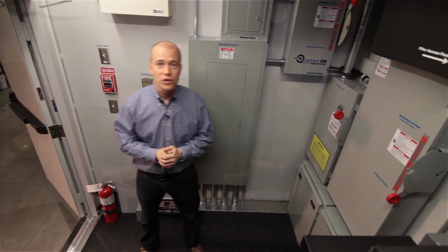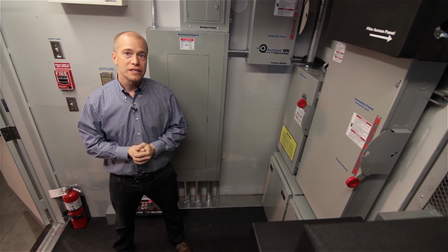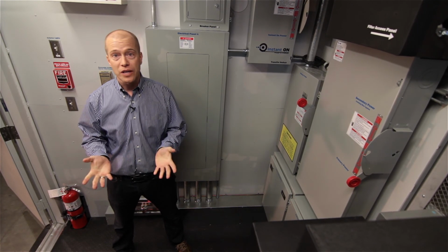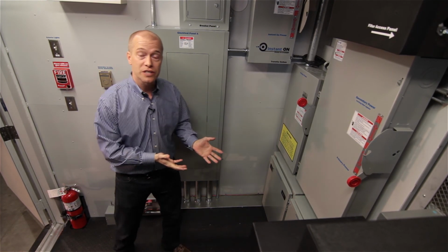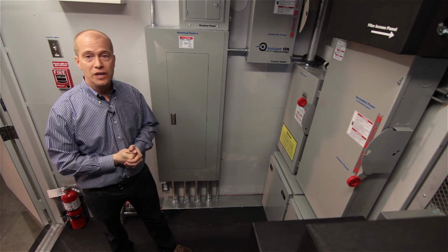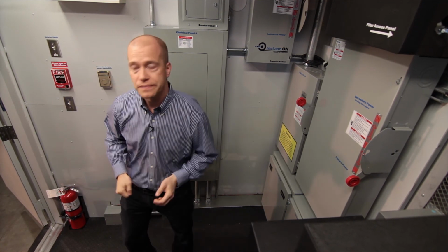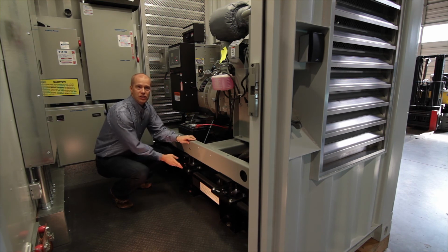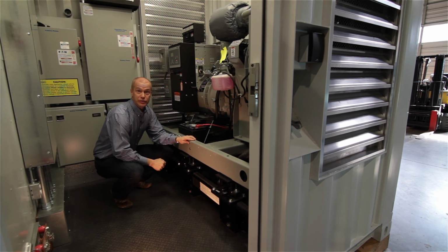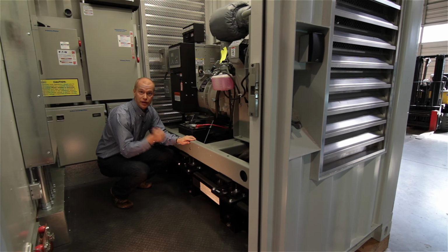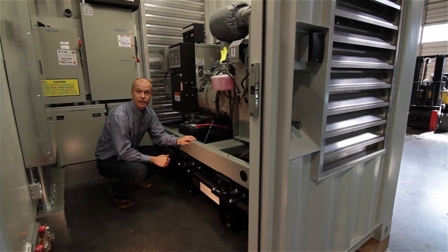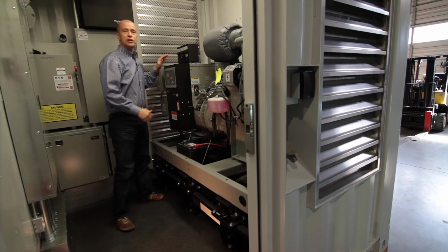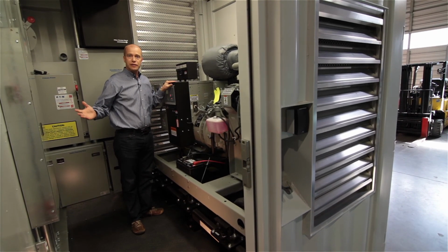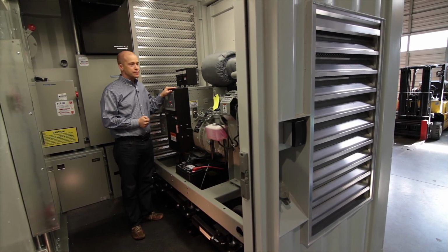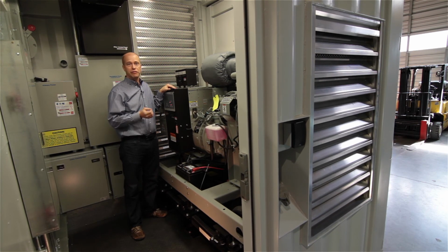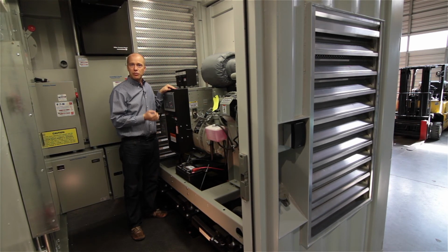This unit has a 3-zone architecture. Zone 1 is the electrical room, where we have a 50 kilowatt generator, automatic transfer switches, and all the components to power the unit. Let's take a look at some of the features in more detail. We've installed some isolation springs that dramatically reduce the vibration of the generator that might affect the equipment in the IT racks. We've also installed a lot of monitoring from end to end in the unit, particularly in the electrical room. We're monitoring everything on the generator from fuel levels to inputs, outputs of electricity.